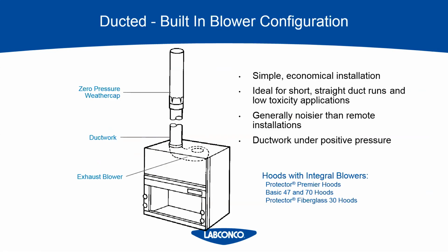Whenever you look at these, the manufacturer is going to have a certain maximum amount of duct that you can have on this system, because every time you add that duct, that's adding static pressure or resistance to that duct run. So the fan can only overcome a certain amount of extra resistance. These setups are typically louder because the fan is right on top of the hood. So I wouldn't recommend this type for any kind of teaching lab, any lab where noise is a factor.